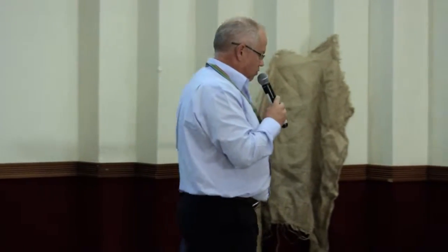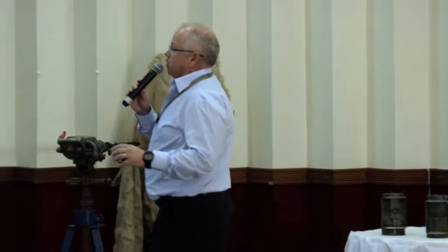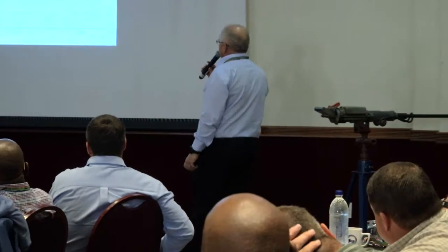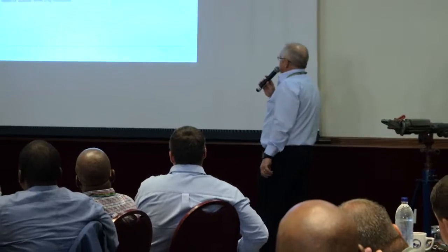Typically, it depends on the environment underground, and what Mornay said earlier is very, very true: you can put all these nice things together, but if you're going into a confined space, if you go into a 70 centimeter stope, the picture changes significantly. So the microphone positions should be, for standing persons, 1.5 meters above the floor, and for seated persons, 0.9 meters above the seat.